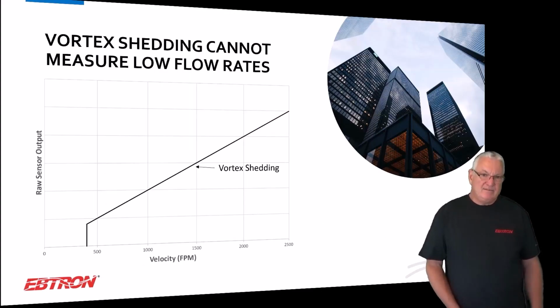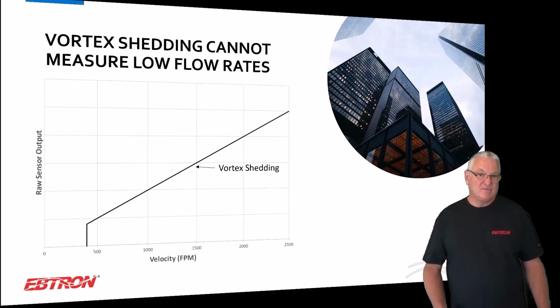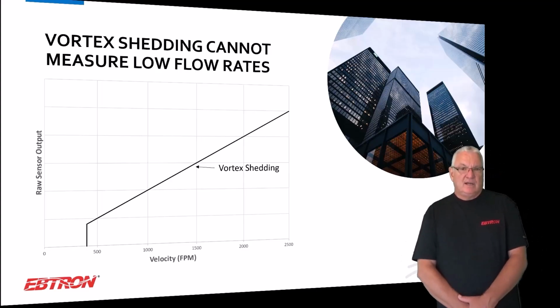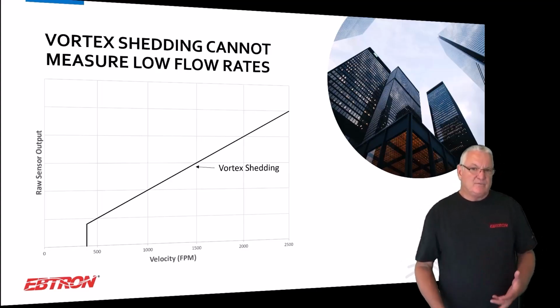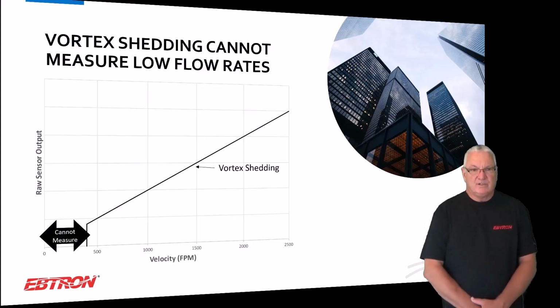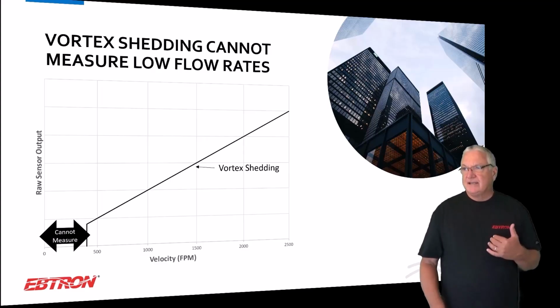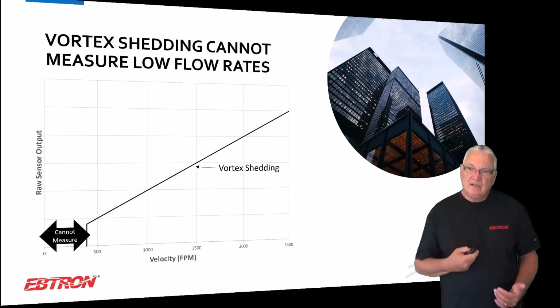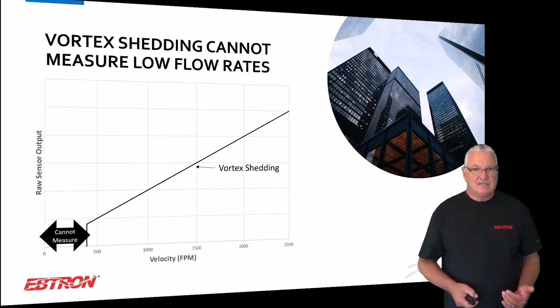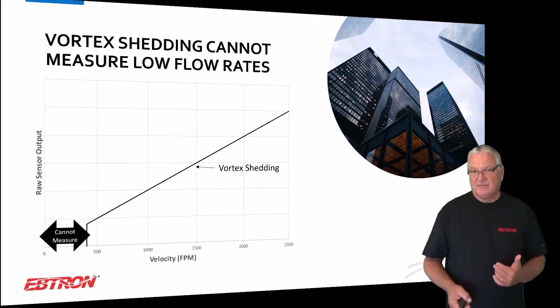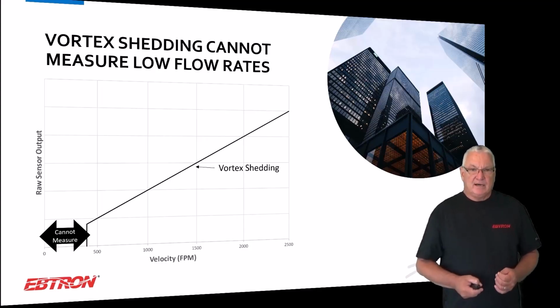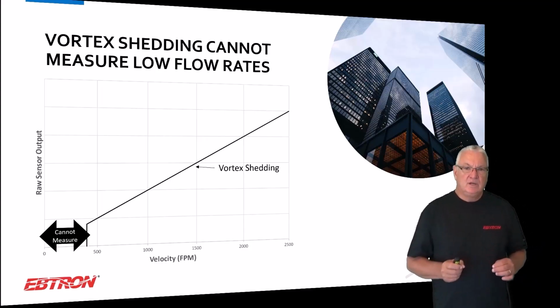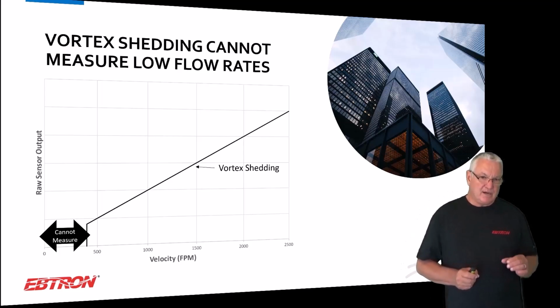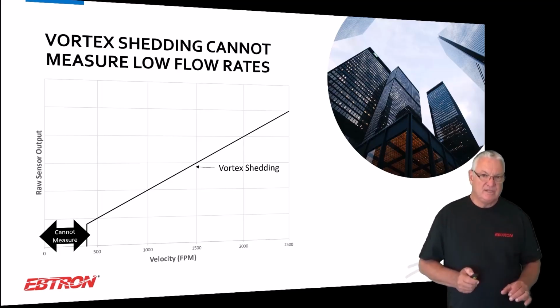And then, finally, vortex shedding, it's out there. It's been out there for almost, I would say, as long as we have been around. And one of the bigger problems with vortex shedding is that it just can't measure lower flows. Basically, they're measuring low audio frequencies. The response is somewhat linear to flow, which isn't bad, but it's airflow, not mass airflow. And so the problem is primarily lower flows with these devices.